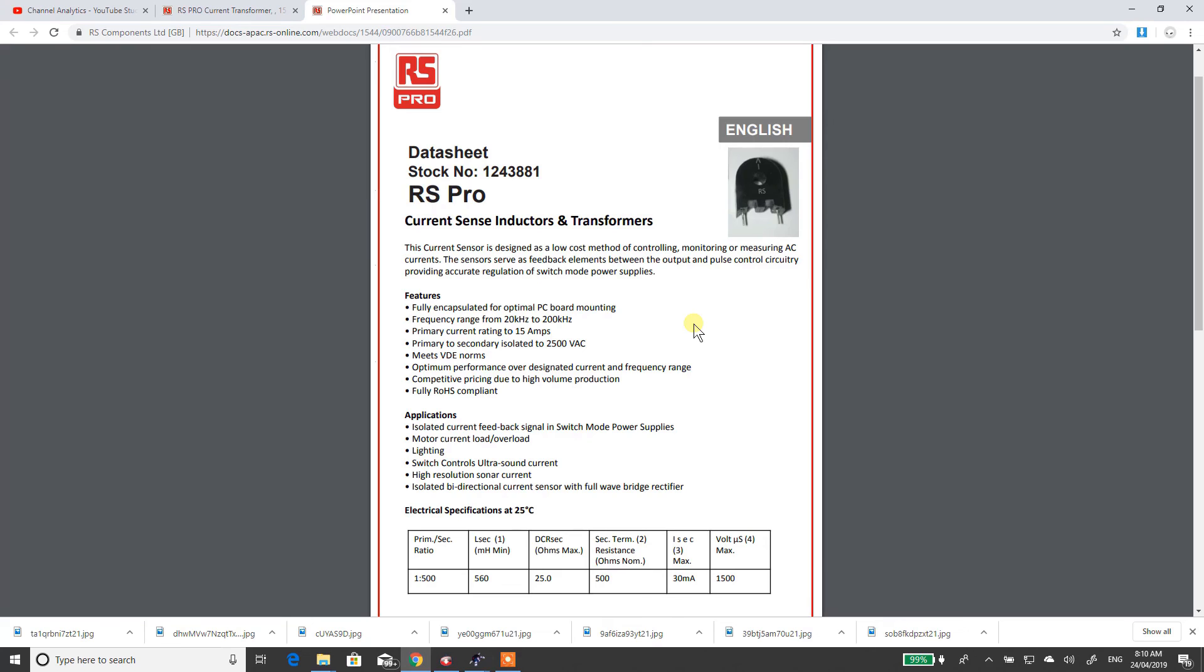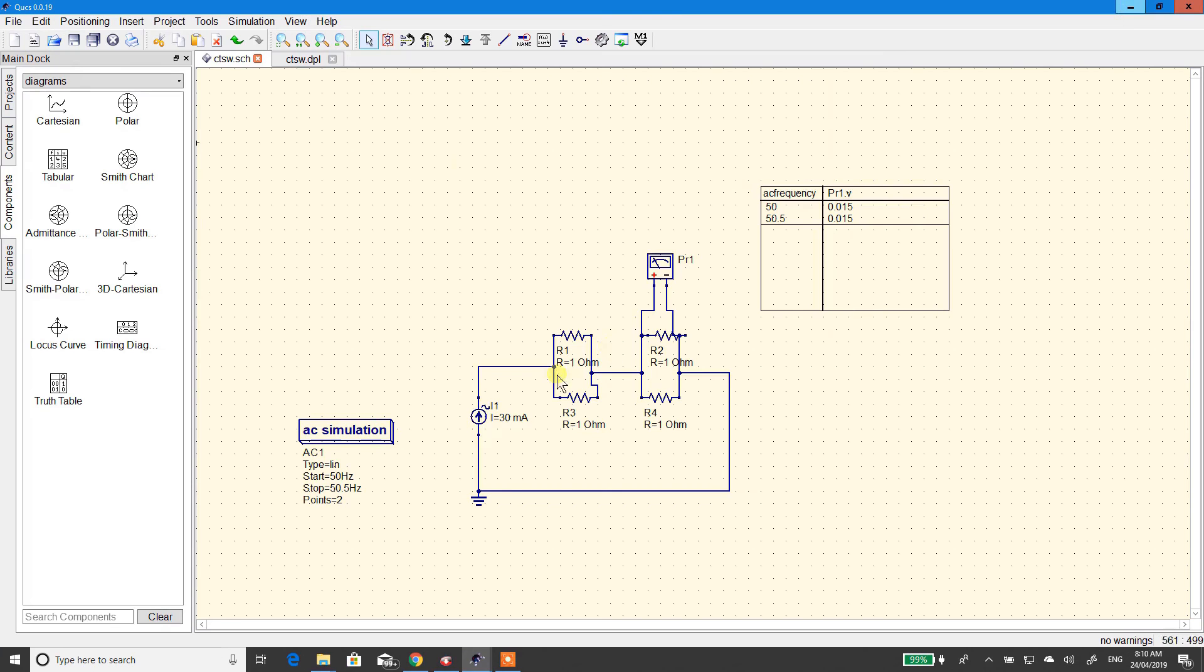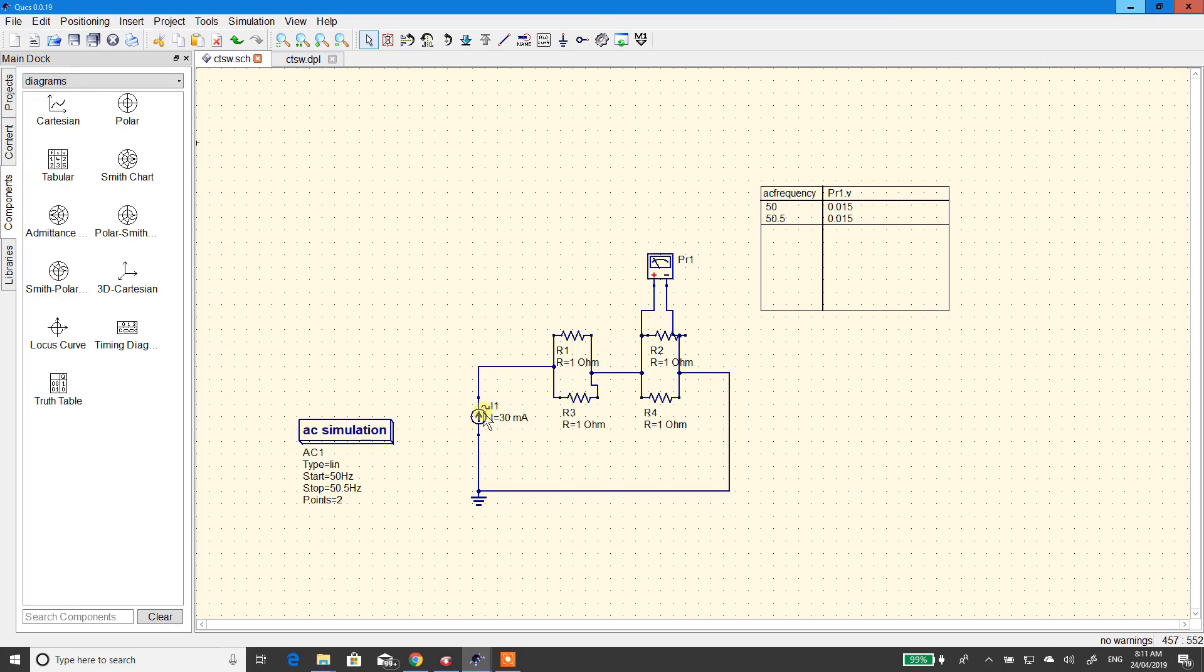Alright. The most important thing to think about when you're selecting your CT is the primary current and the secondary current. So, when there's 15 amps flowing, there's 30 milliamps flowing in the secondary side. Now, that's why I made this value 30 milliamps. Make this value whatever the current that is flowing in your secondary circuit.